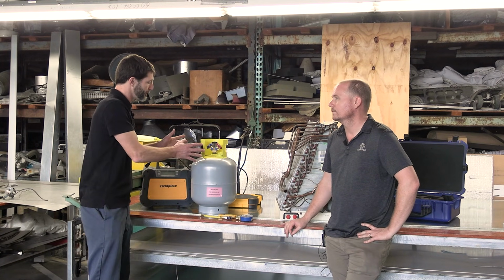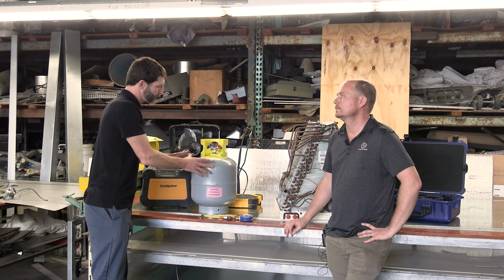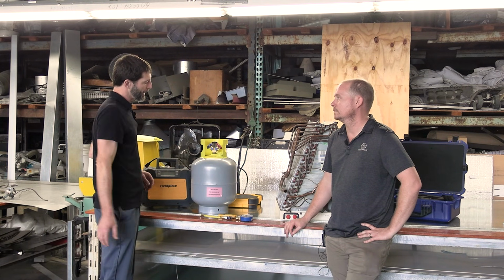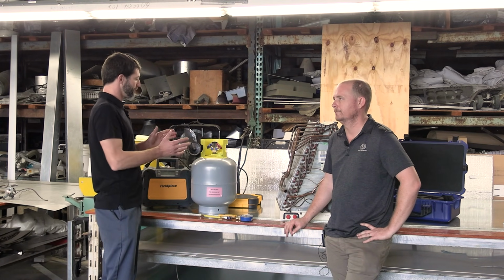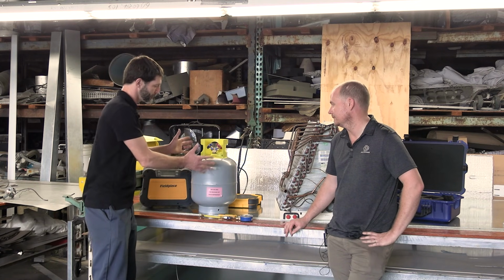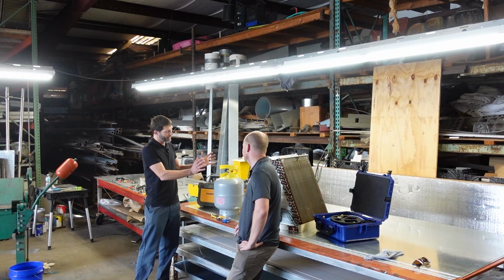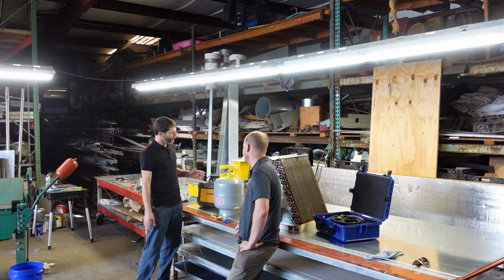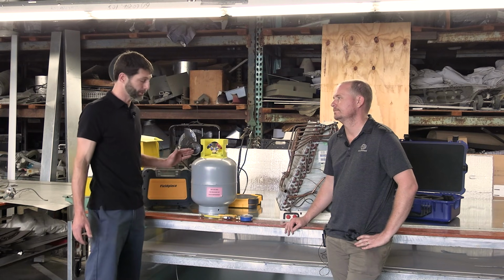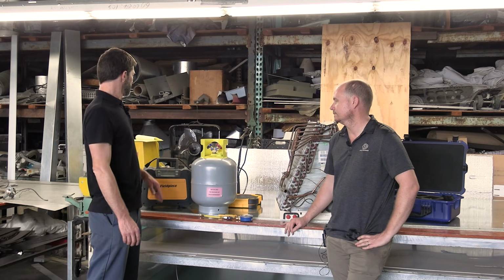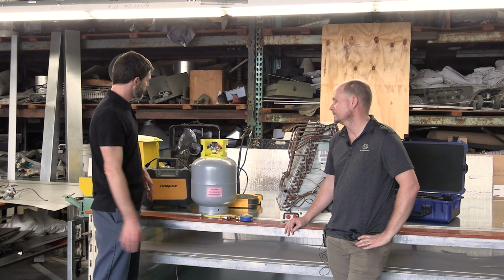I wouldn't vacuum this recovery bottle at your shop and then close the valves and then take it to the job site and then think you're still holding vacuum. I would do that on the tank right before using it and adding your refrigerant into the recovery bottle here. So this can be referred to as a recovery bottle or recovery tank.